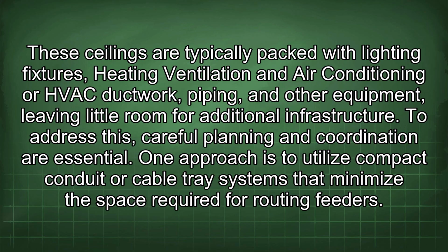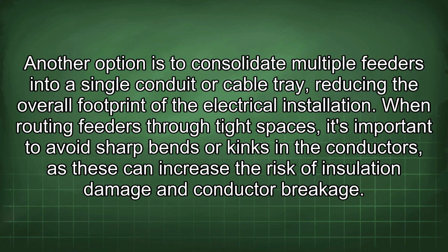These ceilings are typically packed with lighting fixtures, heating, ventilation and air conditioning or HVAC ductwork, piping, and other equipment, leaving little room for additional infrastructure. To address this, careful planning and coordination are essential. One approach is to utilize compact conduit or cable tray systems that minimize the space required for routing feeders. Another option is to consolidate multiple feeders into a single conduit or cable tray, reducing the overall footprint of the electrical installation. When routing feeders through tight spaces, it's important to avoid sharp bends or kinks in the conductors, as these can increase the risk of insulation damage and conductor breakage.